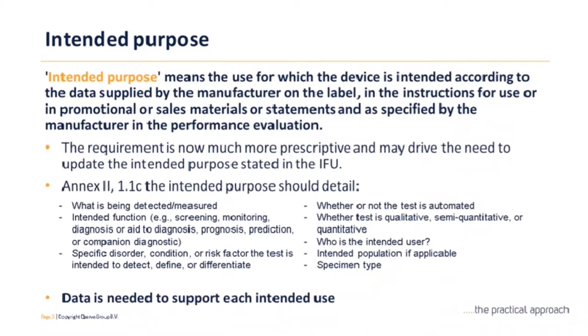You also have to define whether it's automated, whether it's qualitative, semi-quantitative, or quantitative, and who your intended user is. Particularly important because there's much more requirements about near-patient testing. So is it intended to be used in a doctor's office, or an ambulance, or even an air ambulance, because the requirements will be quite different. And then you have to say who your intended population is, and also what specimen type you intend your product to be used for. And ultimately, you're going to need data to support all of these that you describe as part of your intended purpose.